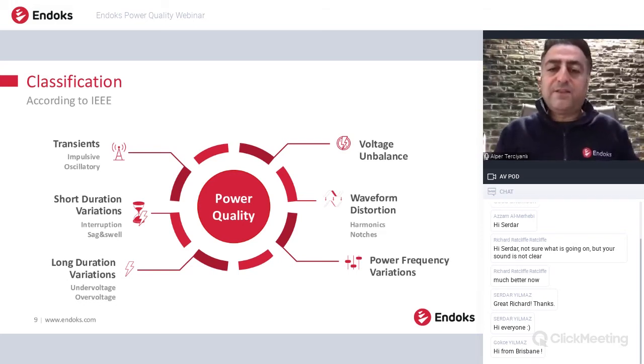The other thing is frequency variations, which, in Australia of course, and in some countries, arise especially because of the imbalance between demand and generation, and also the variation of generation, if it comes mostly from wind, solar and other renewable and varying resources. Then the frequency variation becomes very important. To support these variations there are market operations, the frequency ancillary services, and on the other side the primary frequency control. Frequency is also important because most equipment, especially motors and generators, is designed to operate at a certain frequency. And these are the parameters.